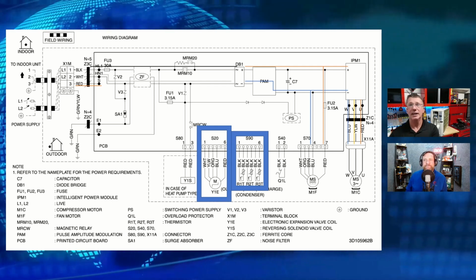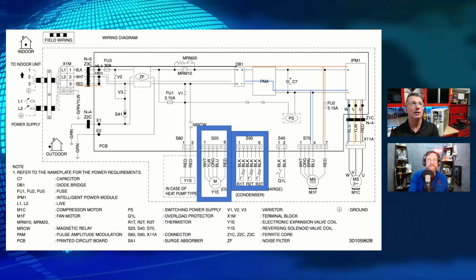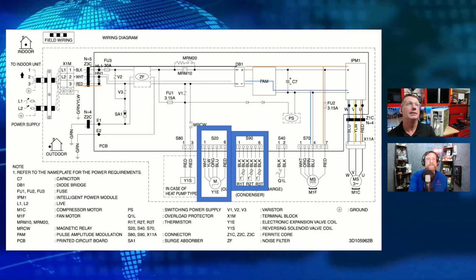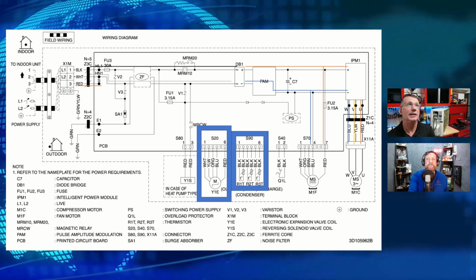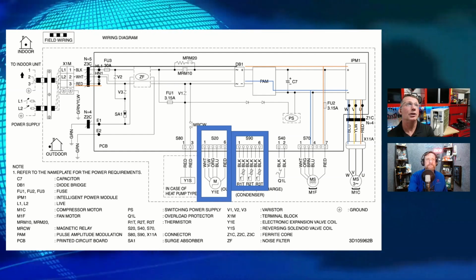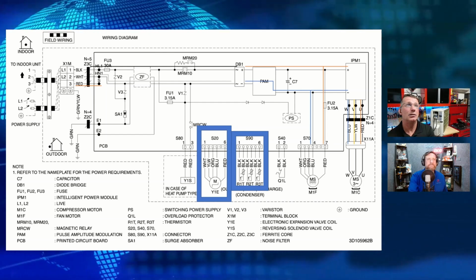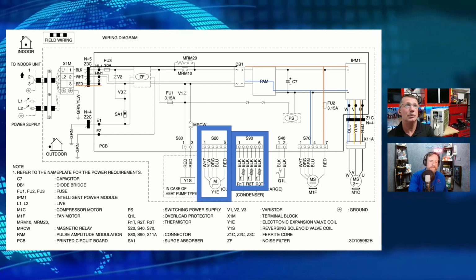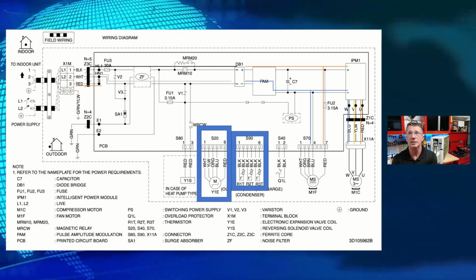Yeah, absolutely. We can look at any of these wiring diagrams and it will tell you without telling you the importance of a dedicated ground circuit. Like if we look at this particular one, our incoming power is coming in over here at power supply. So this particular one would be our 240 volt system with L1 and L2, and its ground is passing through. It is connecting on the ground terminal and going directly back into that indoor board. And if we look at our communication, number 1, number 2, number 3, and then its dedicated ground going to the indoor unit, it is also grounding onto that same terminal. And number 3 is going to be that communicating signal. So if we have any interruptions in our ground signal, it will be able to have an interference with our communication circuit.